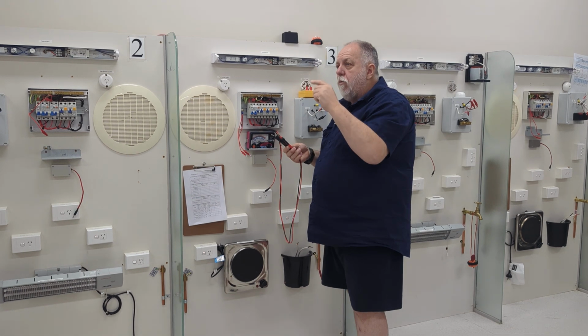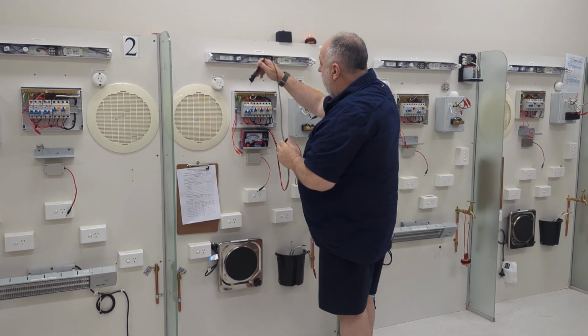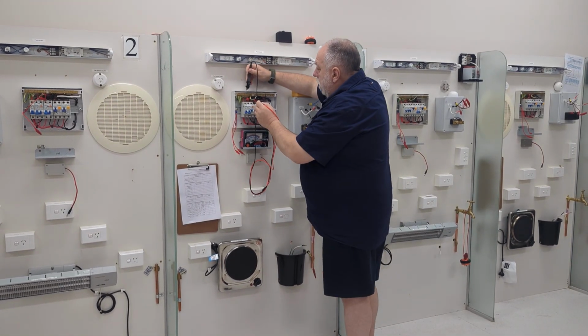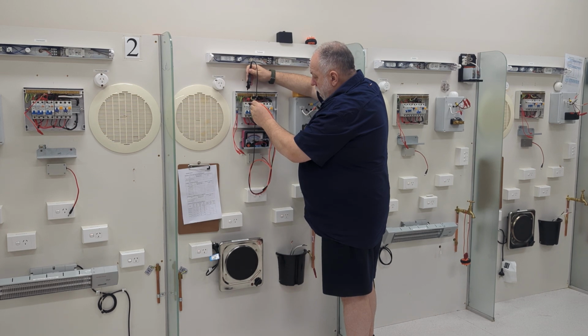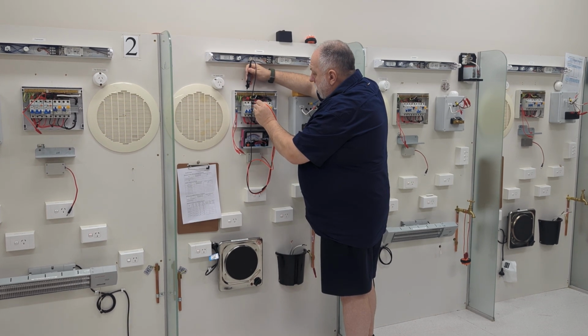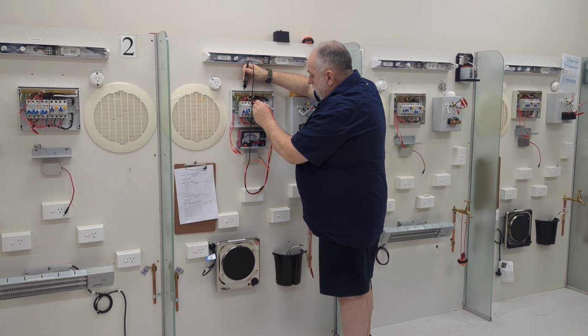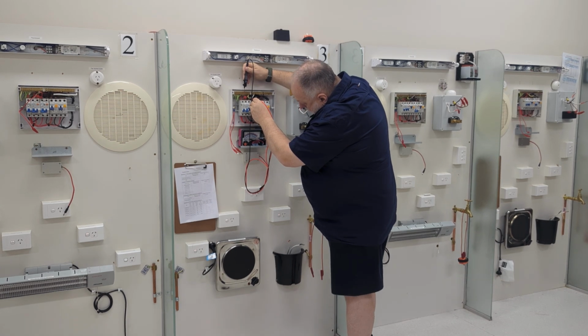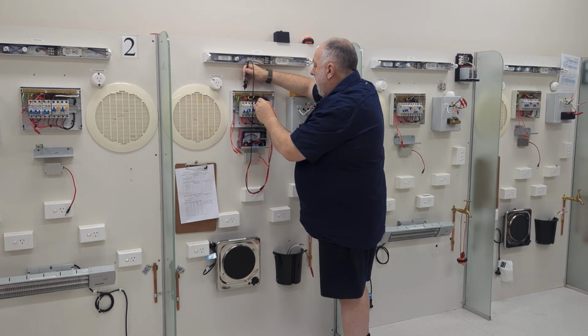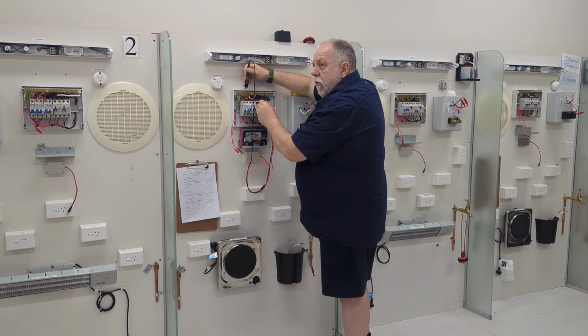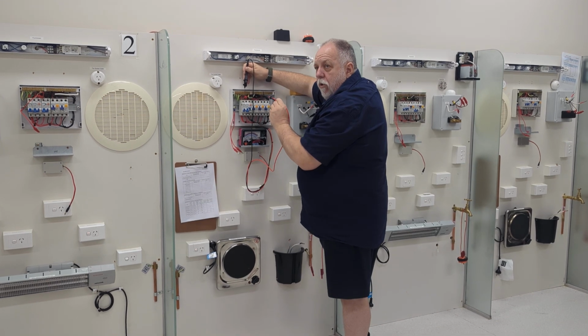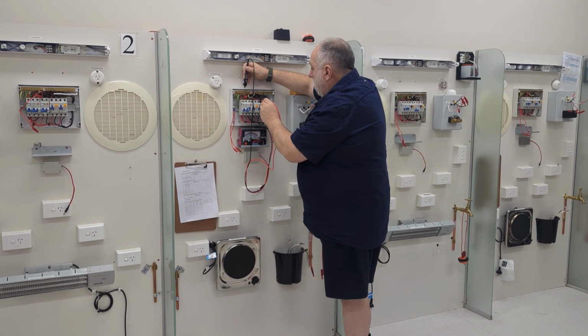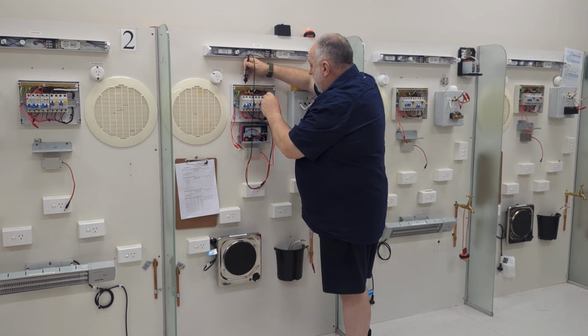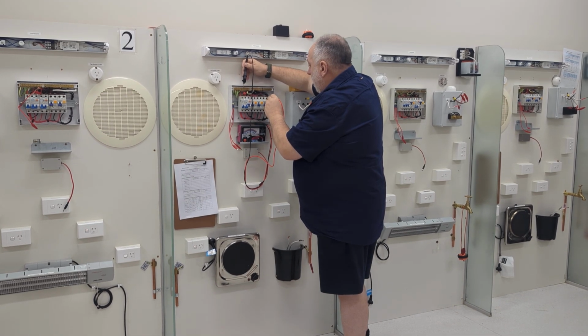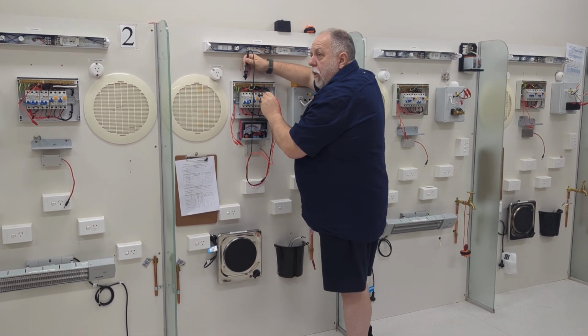So what I do is, as we go down, I go to earth, I work my way along the top, that's okay, the lighting circuit, beautiful. I've now got a reading down to 0.6 of a meg on the active, 0.6 on the neutral, so both active and neutral on the lighting circuit are affected. I'm getting nothing on the power circuit. So my fault is now on the lighting circuit.